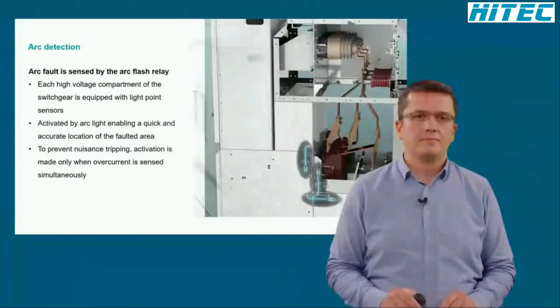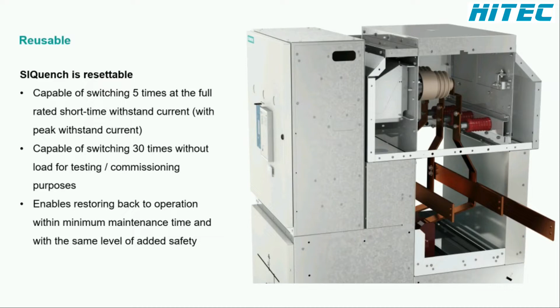SIQuench has a unique feature. It is reusable, or we can call it resettable. So the switching operation in the case of an arcing fault is reversible. Resetting is done from the front of the panel without the need for opening any covers or even any doors. It can withstand 5 consecutive switching operations with the full rated short time withstand current of the switchgear. It also allows for 30 real physical switching operations without load for testing and commissioning purposes.